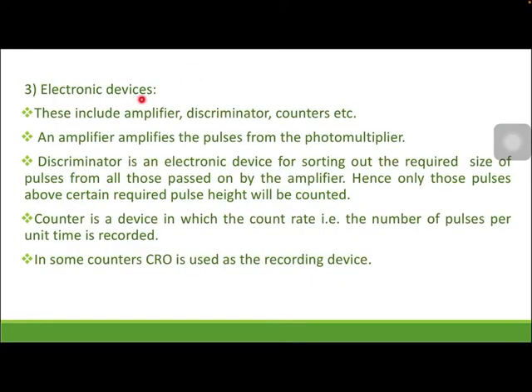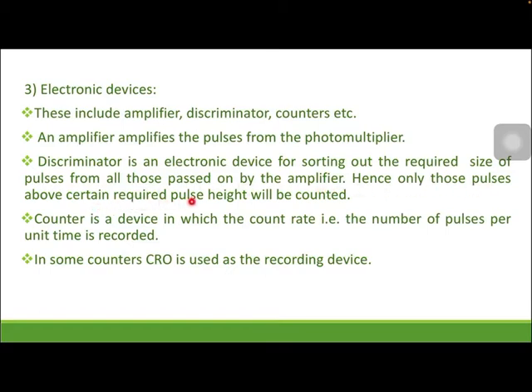The third part consists of the electronic devices, which include amplifier, discriminator, and counter. An amplifier amplifies the pulses from the photomultiplier. A discriminator is an electronic device for sorting out the required size of pulses from all those passed on by the amplifier; only those pulses above a certain required pulse height will be counted. A counter is a device in which the count rate — that is, the number of pulses per unit time — is recorded. In some counters, a CRO is used as an electronic counting device.